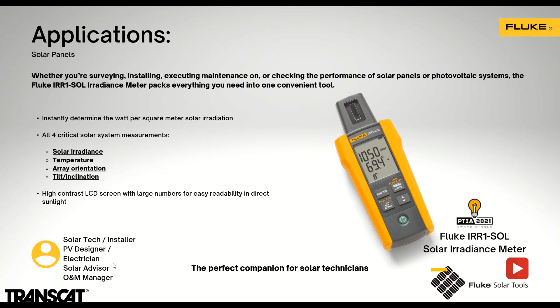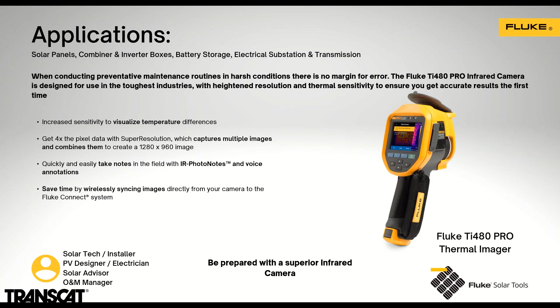So now I'm going to talk briefly—we've got some more slides to go through. We've talked about the voltage and current and everything we can do on the output of those panels, and we can talk about the irradiance, but these systems take so much more into account. Thermal imagers are a key tool to visually look at those panels and make sure there are no fracture cracks in them; you can see if the diodes have even been blown out. Having a good thermal imager really helps in every aspect of that solar system, whether it's at the panels, the combiner boxes, the inverter boxes, even on battery storage, and then moving up even further to substations and transmission.